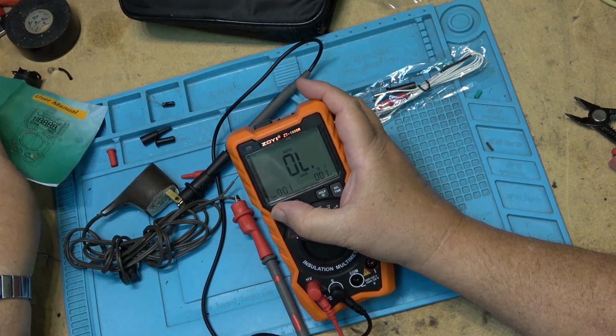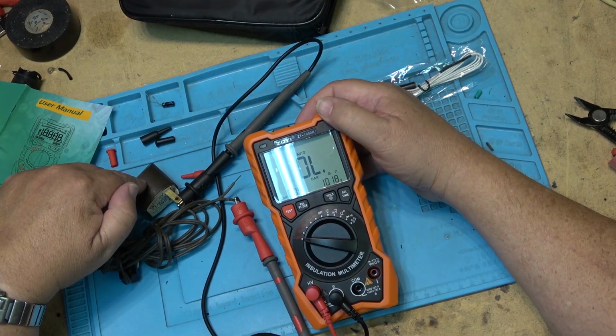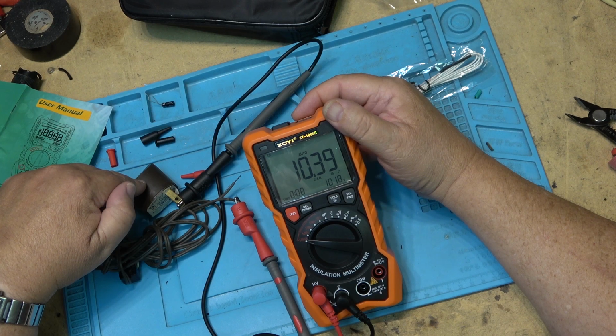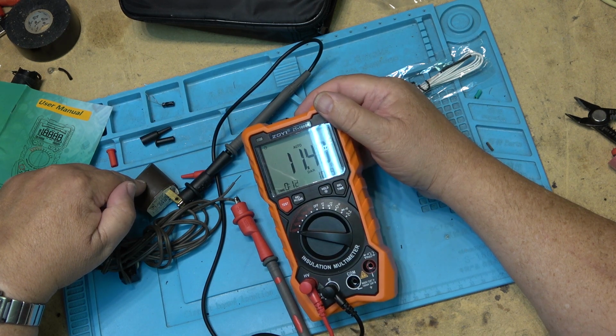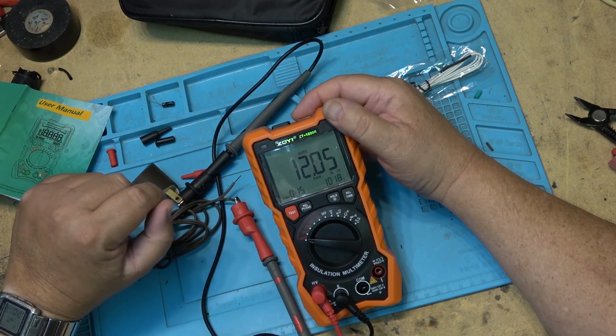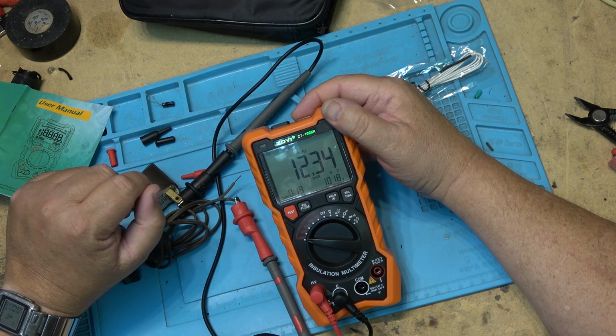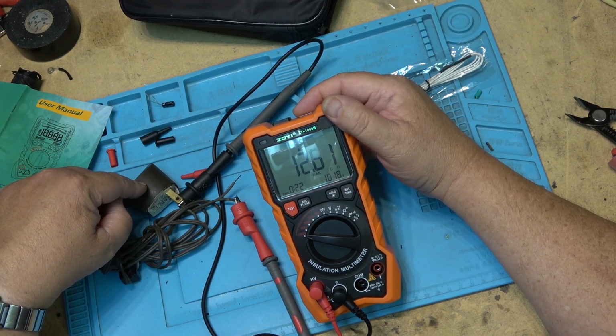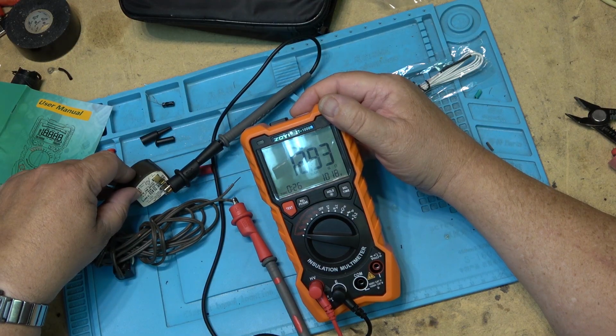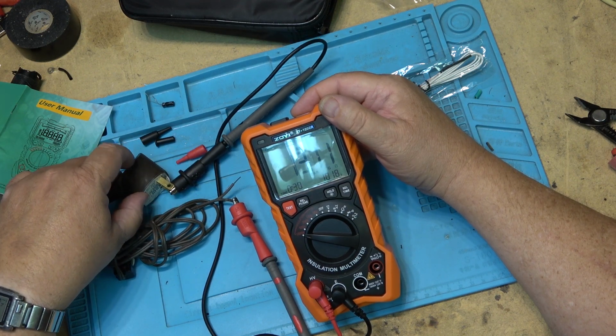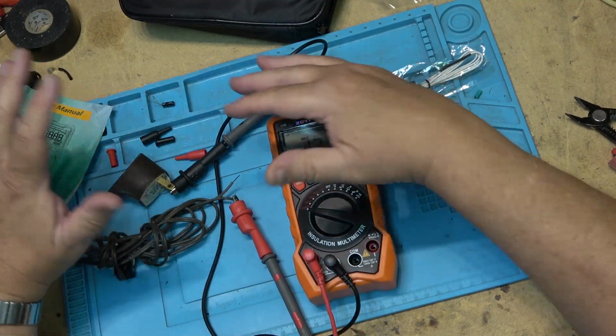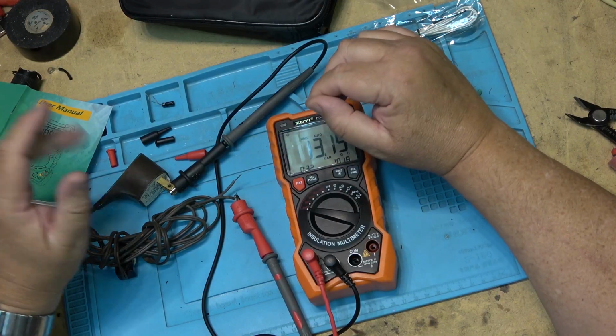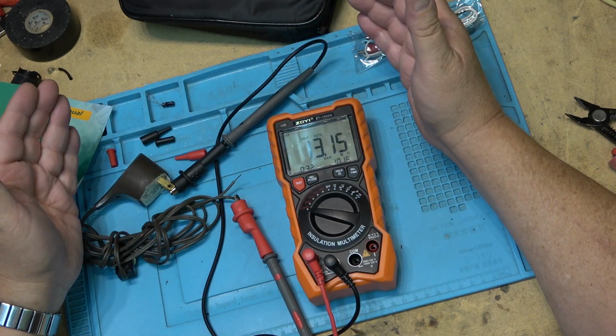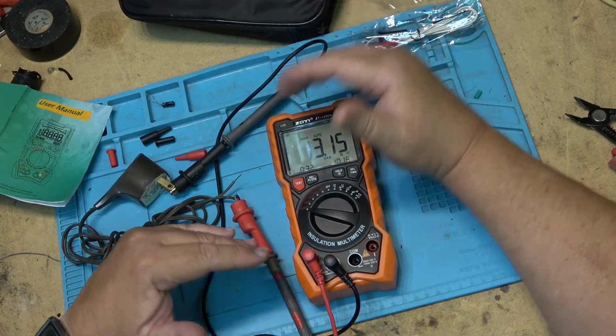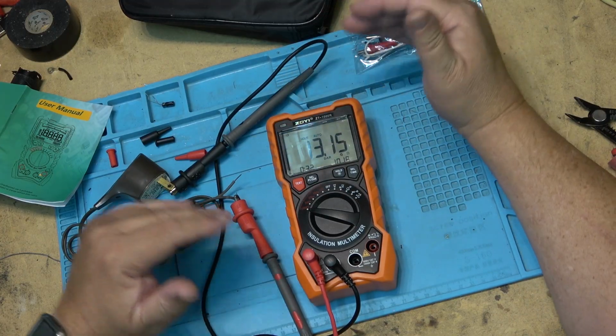And if I switch that off and switch it to DAR, dielectric absorption ratio, this will give me an idea of how the dielectric is holding up. And is it breaking down? This is obviously having an effect on the transformer because the numbers are changing. But that's at 1000 volts, and this transformer is just 120 volts down to 7 volts AC output. But that gives you an idea what the meter's for. It's designed for testing motors, transformers, anything where there could be a breakdown. Even between your radio and a chassis, to see what your isolation is between your hot circuit and your ground.